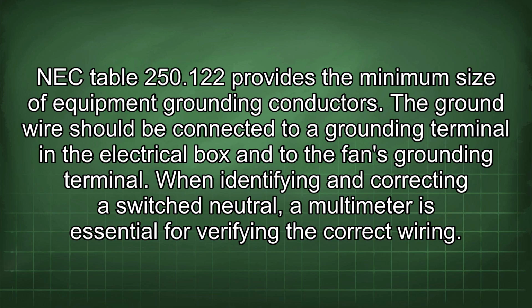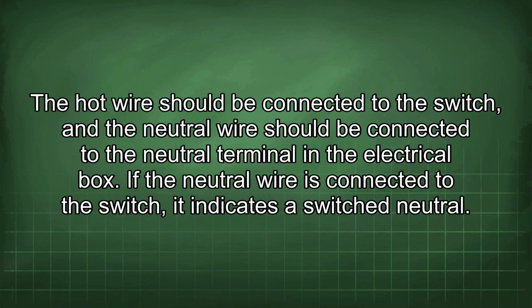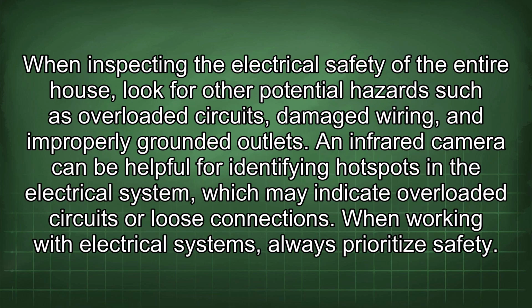When identifying and correcting a switch neutral, a multimeter is essential for verifying the correct wiring. The hot wire should be connected to the switch, and the neutral wire should be connected to the neutral terminal in the electrical box. If the neutral wire is connected to the switch, it indicates a switch neutral. When inspecting the electrical safety of the entire house, look for other potential hazards such as overloaded circuits, damaged wiring, and improperly grounded outlets. An infrared camera can be helpful for identifying hotspots in the electrical system, which may indicate overloaded circuits or loose connections.